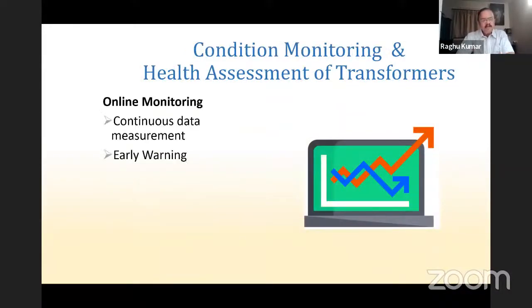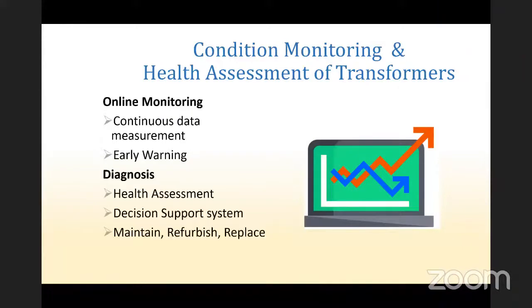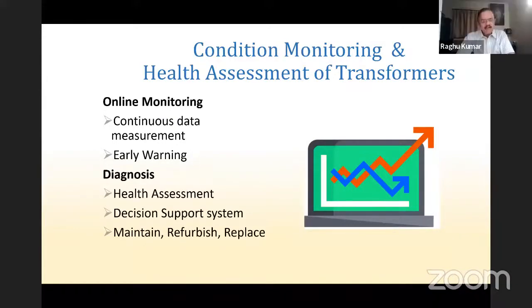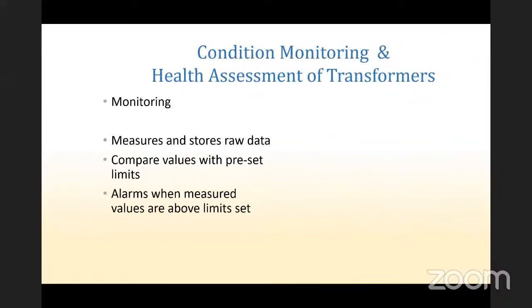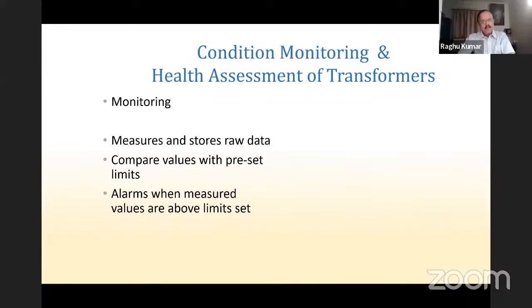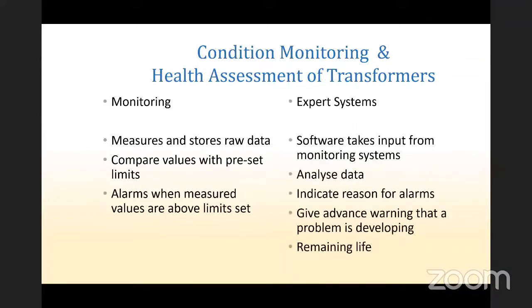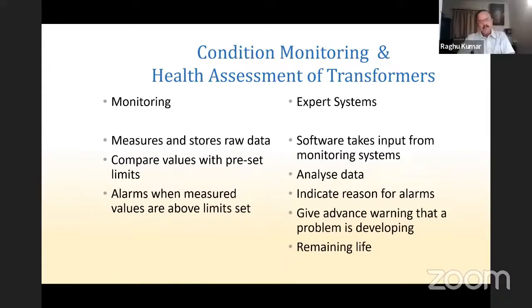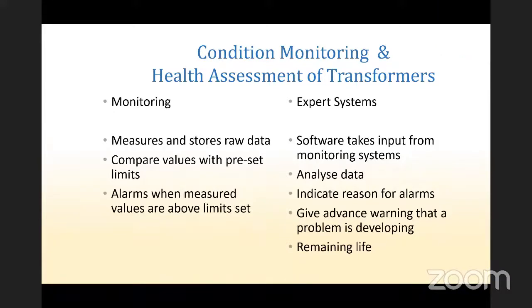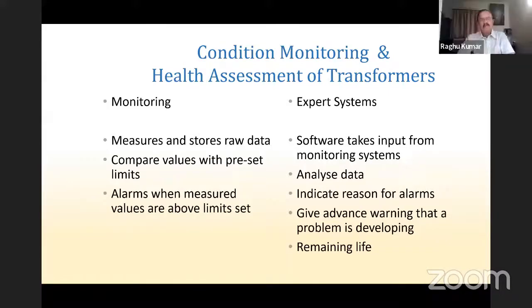So online monitoring is a continuous data measurement. It gives you an early warning system. And diagnosis is the health assessment. It's a decision support system which helps you to make maintain, refurbish or replace decisions. Monitoring basically measures and stores raw data, compares the values with preset limits, and raises alarms when measured values are above a set limit. In expert systems, software takes the input from the monitoring systems, analyzes this data, indicates reasons for the alarm, gives advance warning that a problem is developing, and the remaining life of the transformer is calculated.